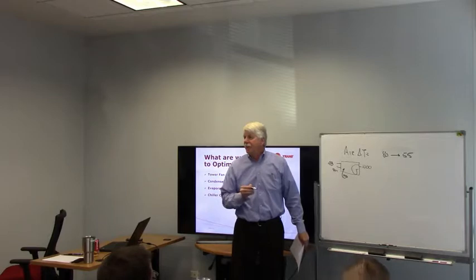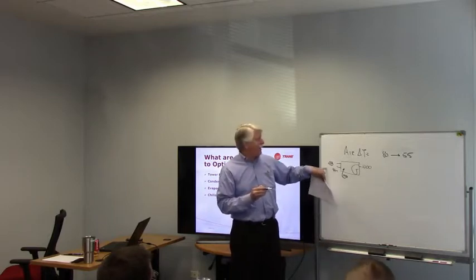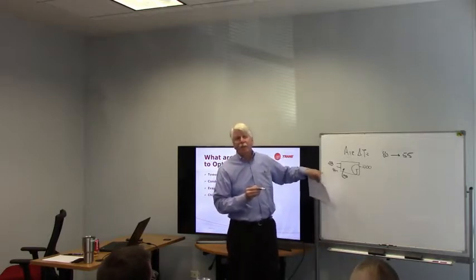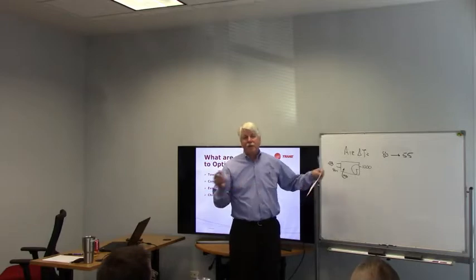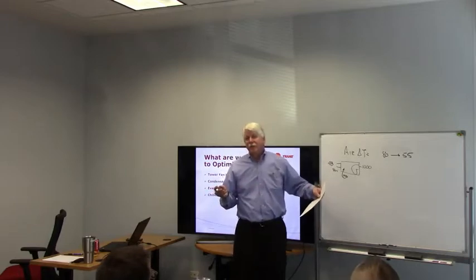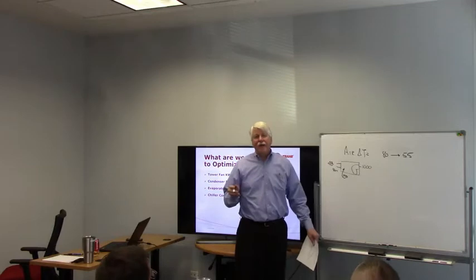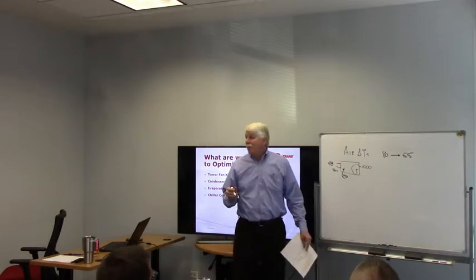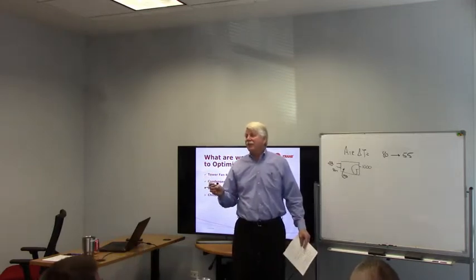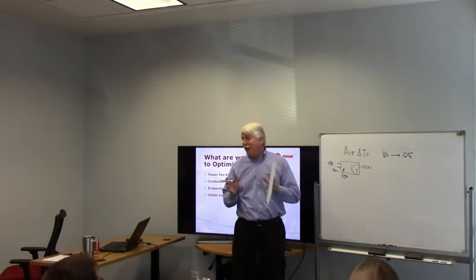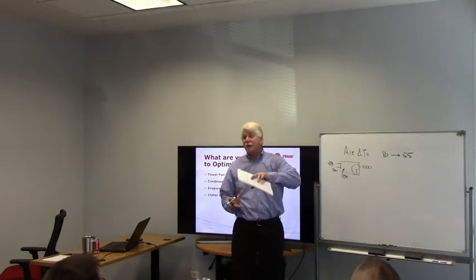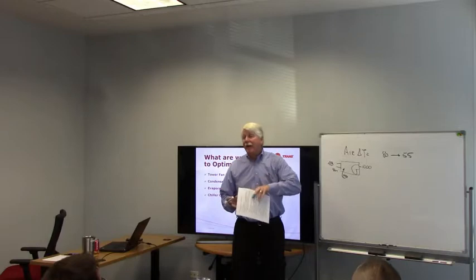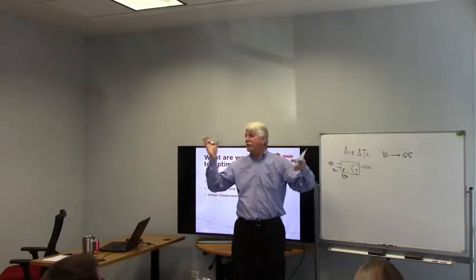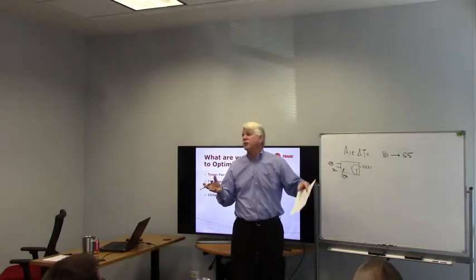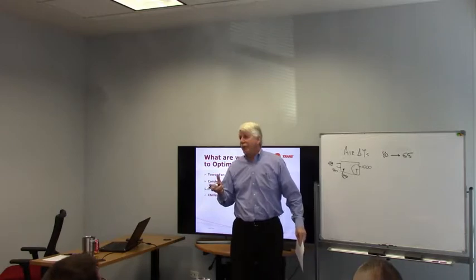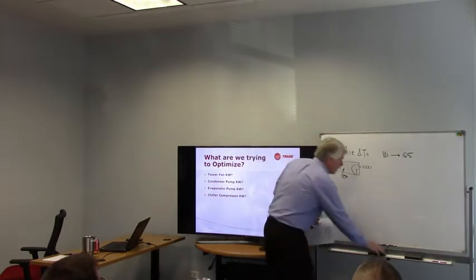All right? Now, you might ask, why do you do 48-degree air? Well, everything is based on delta T. So if I have 48-degree air, the amount of CFM I have to send is substantially less. So your supply ducts get smaller. That helps in the plenum space in the buildings where they're putting ductwork in because you're using smaller ductwork. So that's why you use cold air. Okay.